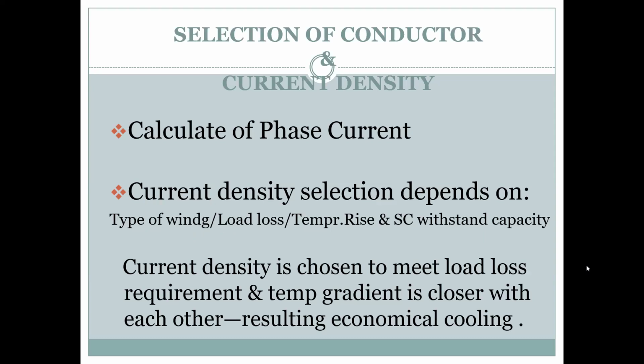Next. Calculate phase current, root 3. Then current density; the selection depends on what type of material you are using, load loss, temperature rise. Your IS gives you the guidelines that for an oil filled transformer, when it runs on full load, the oil temperature should not go more than 50 degrees centigrade, and the winding temperature is the actual one where your temperature starts rising. It should be 55 degrees. But for safer use, every consultant, every user keeps it 5 to 10 degrees lower. So we get inquiries, not as per IS but more stringent than IS, where it should be 45 to 50.